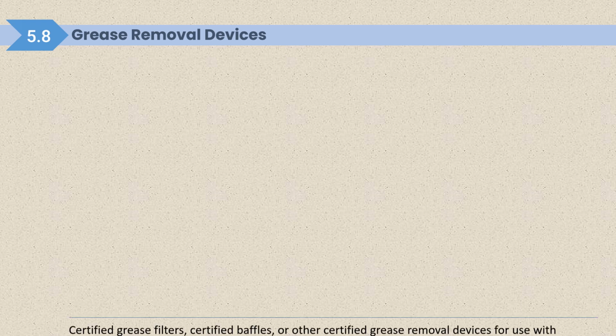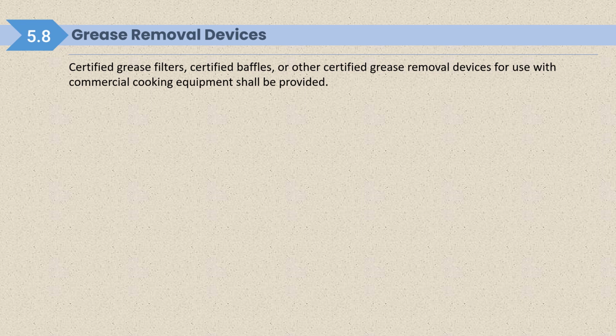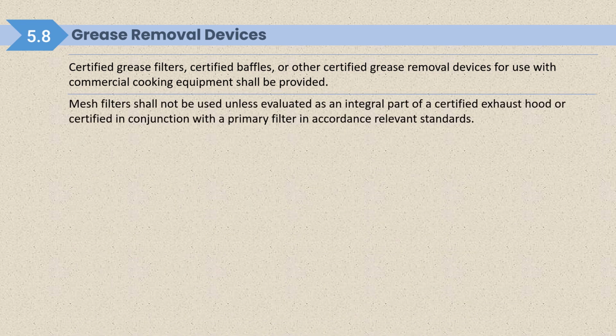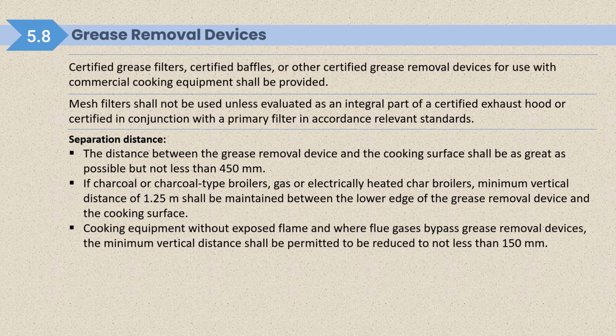In 5.8, grease removal devices are there. So certified grease filters, certified baffles or other certified grease removal devices for use with commercial cooking equipment shall be provided. Mesh filters shall not be used unless evaluated as an integral part of a certified exhaust hood, that we saw in the previous slide. I've shown you the picture also. Mesh filters shall not be used unless evaluated as an integral part of a certified exhaust hood or certified in conjunction with a primary filter in accordance with the relevant Indian standard.